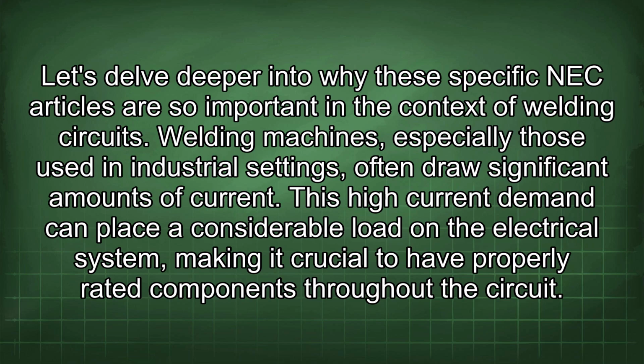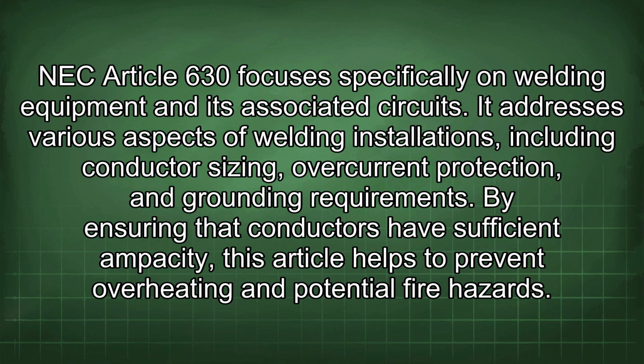Welding machines, especially those used in industrial settings, often draw significant amounts of current. This high current demand can place a considerable load on the electrical system, making it crucial to have properly rated components throughout the circuit. NEC Article 630 focuses specifically on welding equipment and its associated circuits. It addresses various aspects of welding installations, including conductor sizing, overcurrent protection, and grounding requirements. By ensuring that conductors have sufficient ampacity, this article helps to prevent overheating and potential fire hazards.